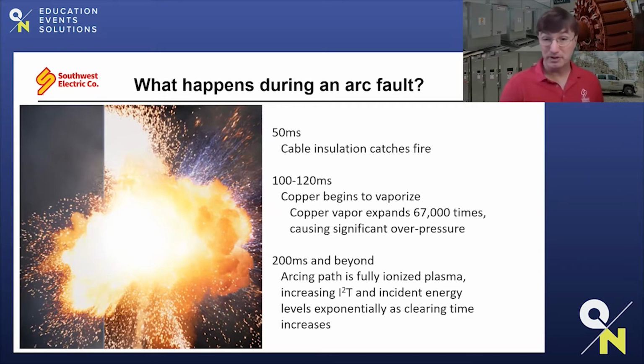After about 200 milliseconds, if the arc is able to continue, if the protection is not sufficient to clear it, you will just increase the amount of ionization, the amount of plasma from the air, and you would only add energy to this event at an exponential rate.